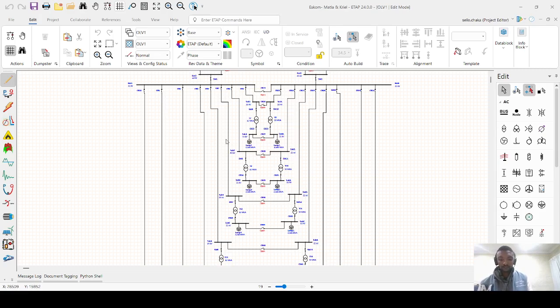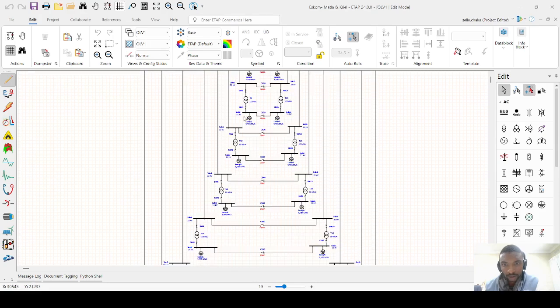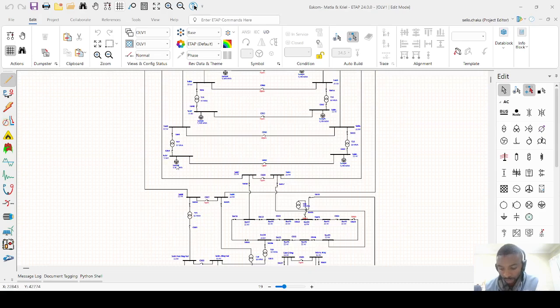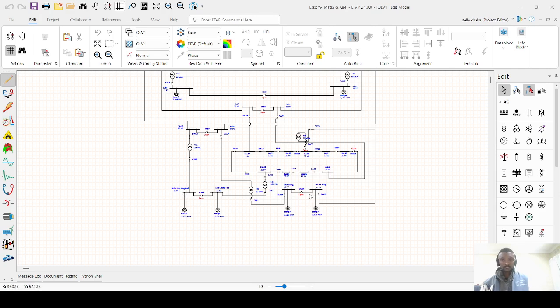Each 11 kV substation is also supplied from upstream, which is already being supplied in a balanced redundant way, as mentioned above. So this is my 11 kV substation, which is connected via these 22 to 11 kV transformers. This will be substation A, B, C up until substation F, and then substations H and G are fed from the radially connected 22 to 11 kV transformers, this one as well as this one, and substations H and G are also fed via the ring network, as shown here. It's fed from here, and it's also fed from there.